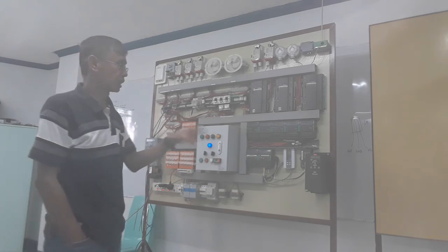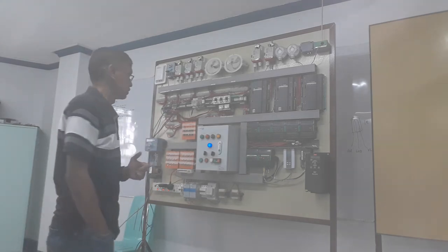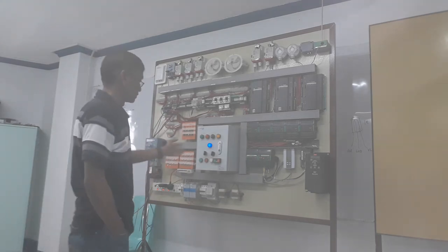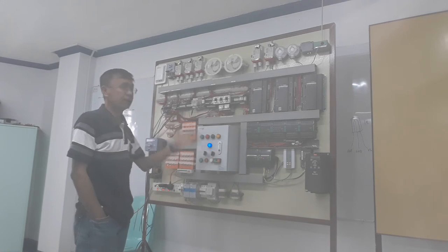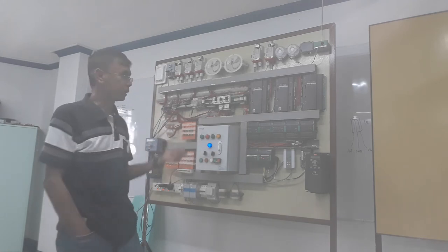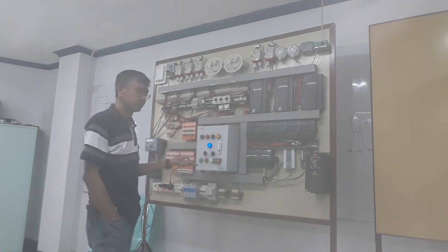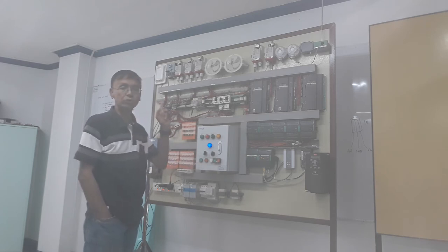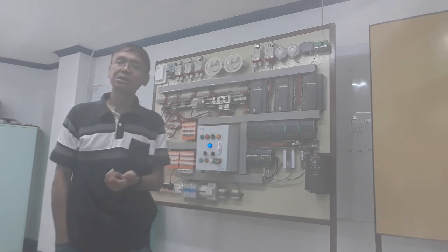This is already programmed by one of my students. When the selector is in hand, the operator or technician can push that start push button so it will work. When it is in automatic, that's the only time your BMS can control it.